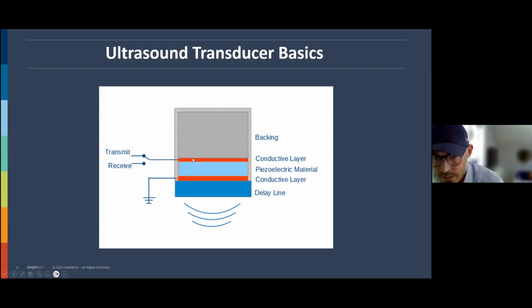So the way to get a transducer to work is that you send in a high voltage pulse on transmit here. So this is a conductive layer. And then you have a conductive layer under the piezoelectric material, which is grounded. So let's say you send a 100-volt pulse in here, and then you're making a potential difference between the top electrode and the bottom electrode. And then this piezoelectric material starts to vibrate. And this vibration causes this sound. It's kind of like a speaker. When you put some electricity on a speaker, it also starts to vibrate and sends out a sound that you can hear. And depending on the thickness of this and so on, that determines the frequency.